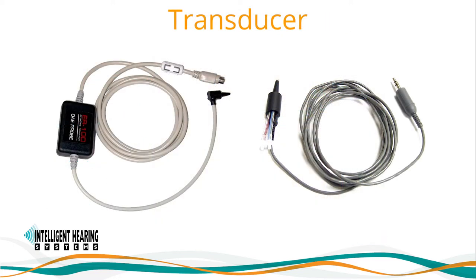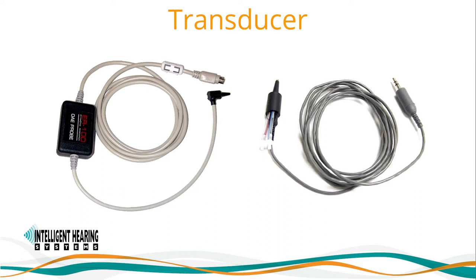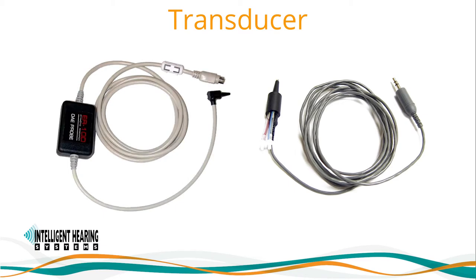IHS devices typically use the 10D OAE probe to clinically acquire OAE responses. A 10D-plus probe microphone can also be used for research applications. How the probe is fitted into the ear canal is one of the most important parts of getting a fast and accurate OAE test.